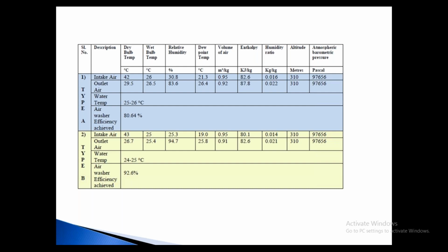So we looked at the intake air, the temperature, the dew point temperature, the relative humidity, and the air wash efficiency achieved earlier versus now. Based on that, the air wash efficiency improved to almost 93%, from 80% earlier. So this kind of modification was done.